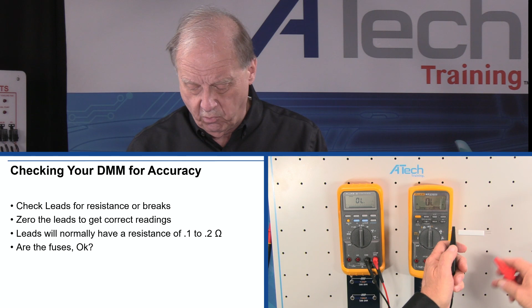Now, if I want to do some other testing, one of the other things I might like to do is hook the leads together, black to black, red to red, and lay them up here. Notice they're both in ohms. The minute I take this thing over and go to voltage, I read on this particular meter 1.25 volts.